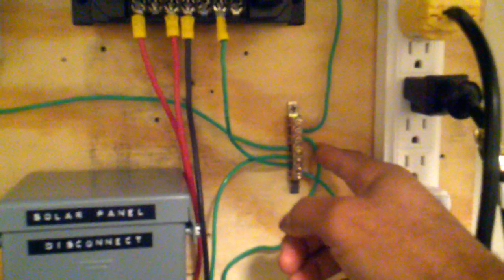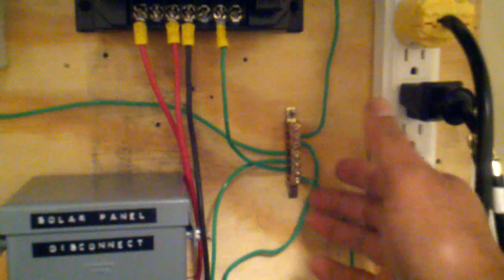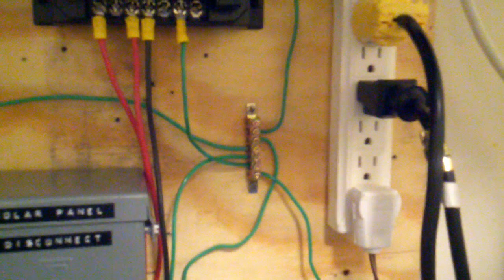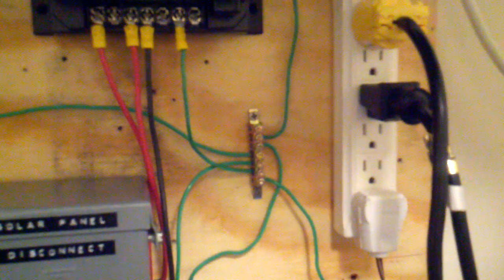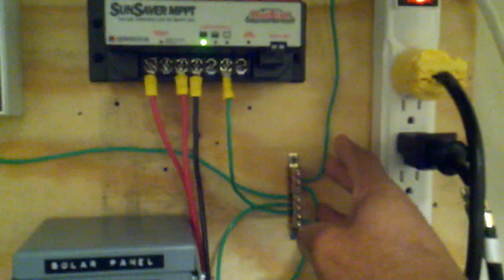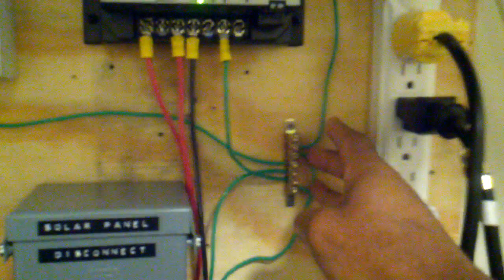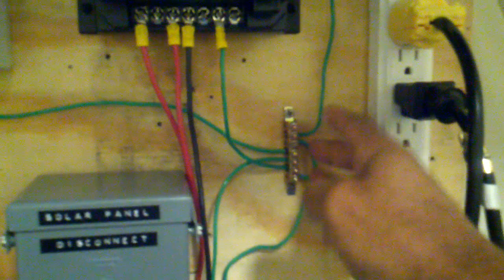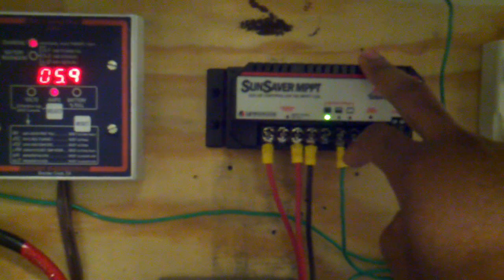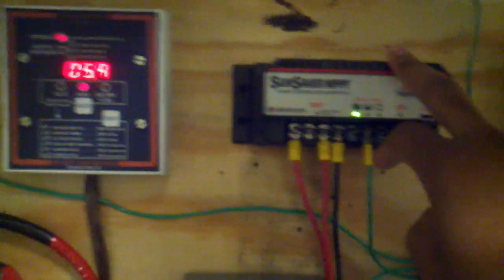Also, I put in a ground bar, because I went through the NEC recommendations. There are two types of grounding. There is the conductive ground and there's the earth ground. This is earth grounded. There's a ground rod on the outside of the house driven into the ground. Basically, some type of steel rod or something. And this right here will ground all of my equipment. I've grounded the charge controllers off the negative lead or the negative input here on the load side. And this is based on manufacturer's recommendations. I've also grounded the switches. These switches are grounded to the rod. Also, my inverter is grounded. So, everything is grounded. My panels will be grounded. The panels on the roof are grounded. And these panels will be grounded also.